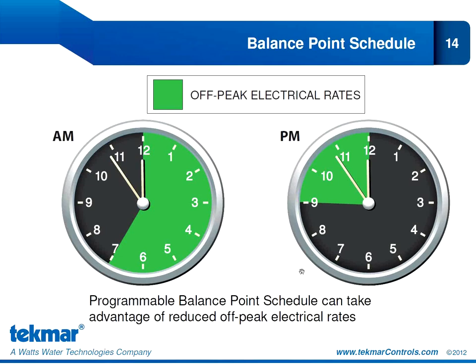Balance point schedule is a new feature for tekmar. As far as I know, the 557 is the only thermostat on the market that incorporates this function. Let's say it's cold outside but we're still above our balance point threshold, so the heat pump is still operating with some efficiency advantage, and our utility company is offering reduced off-peak electrical rates — shown in our diagram from 9 p.m. to 7 a.m. It may make financial sense to only run our heat pump during those off-peak times and use a fossil fuel heat source during peak hours when electrical rates are higher. The balance point schedule function allows us to customize our system to switch between heat sources depending on the financial incentive to do so.